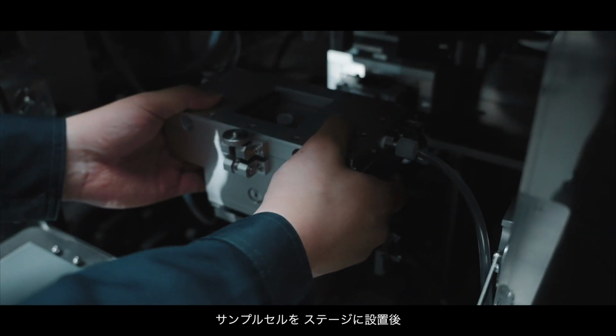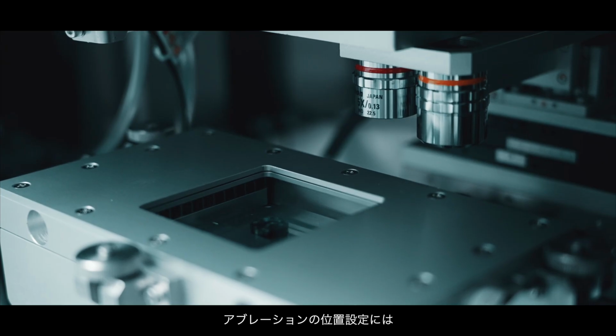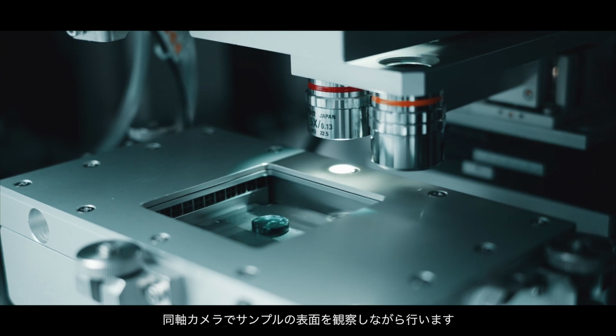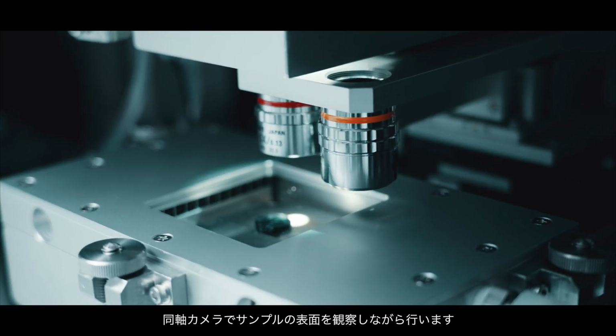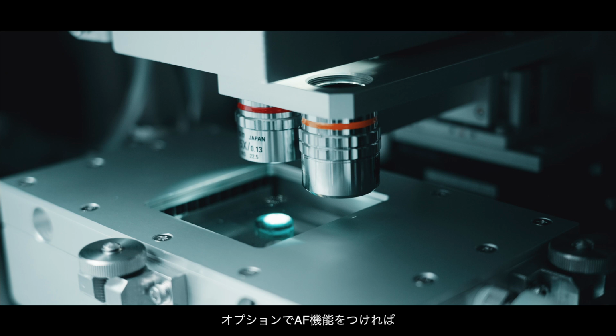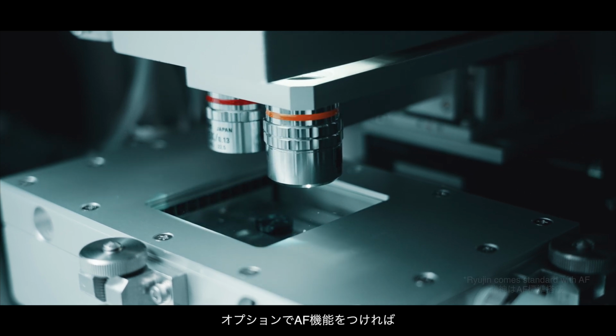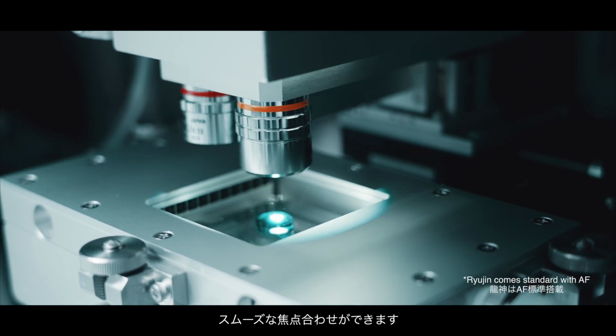After placing the cell on the stage, the ablation position is set while observing the sample with a coaxial camera through these two objective lenses. If you add the autofocus function as an option, you can adjust focus easily.